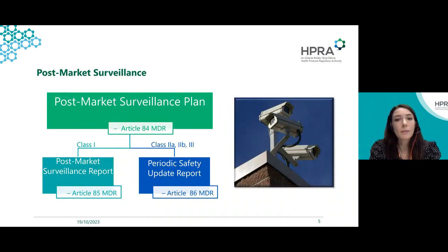So as part of the manufacturer's post-market surveillance system, two key documents must be developed, and they should be included within the technical documentation for the product. The post-market surveillance plan sets out the plans for collection and use of all available information and sets out methods and protocols for fulfilling obligations of post-market surveillance set out in Articles 83, 84 and 86.